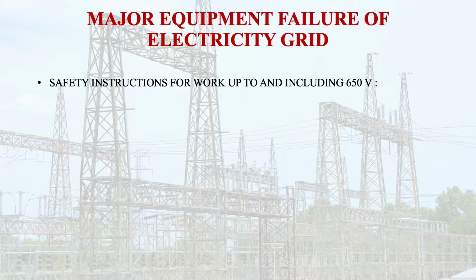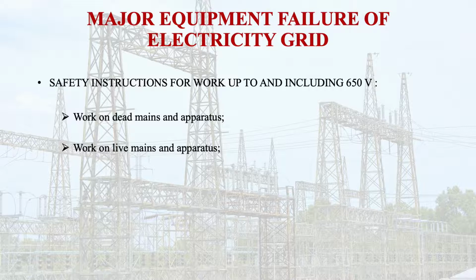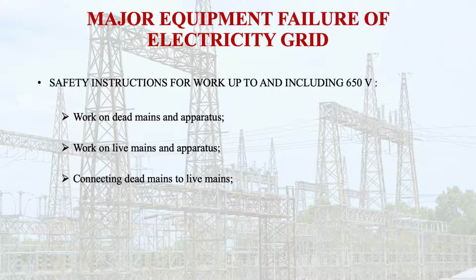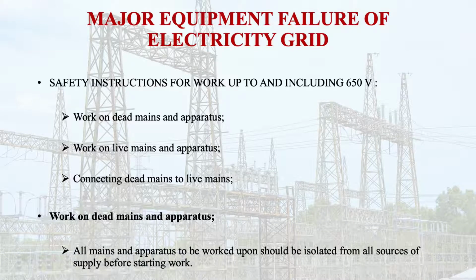So let us discuss the safety instructions for work up to and including 650 volt. When I say up to and including 650 volt, I mean low voltage and medium voltage as defined under the electricity rules. Here we see three parts: work on dead mains and apparatus, work on live mains and apparatus, and connecting the dead line or dead mains to live mains. What are the safety instructions involved in this? Work on dead mains and apparatus means that all mains and apparatus to be worked upon should be isolated from all sources of supply before starting the work.